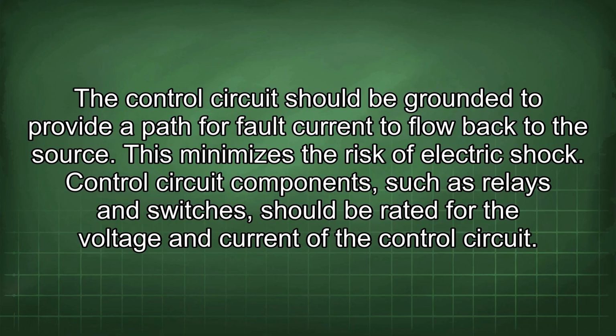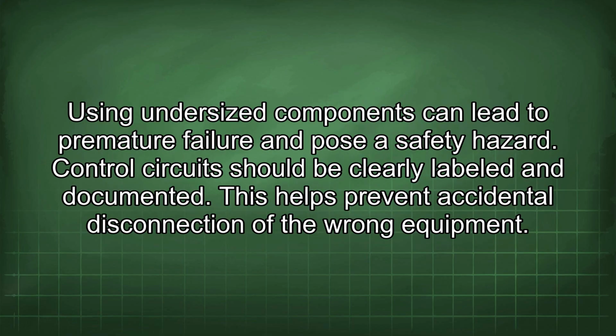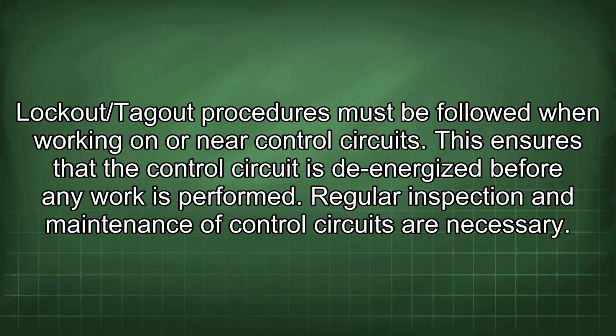Control circuit components, such as relays and switches, should be rated for the voltage and current of the control circuit. Using undersized components can lead to premature failure and pose a safety hazard. Control circuits should be clearly labeled and documented. This helps prevent accidental disconnection of the wrong equipment. Lockout/tagout procedures must be followed when working on or near control circuits. This ensures that the control circuit is de-energized before any work is performed.